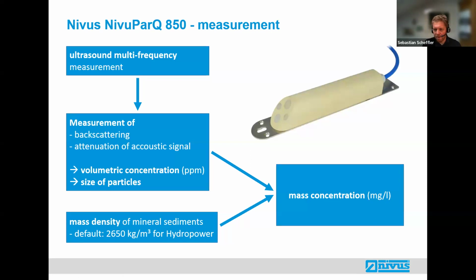If the operator knows by sampling the actual mass density of the mineral, they can also enter this mass density into the system to get an even better measurement. Well, with this measurement of the volumetric concentration and the particle size, and with the mass density that we have to enter into the system, we get the measurement of the mass concentration in milligrams per liter.